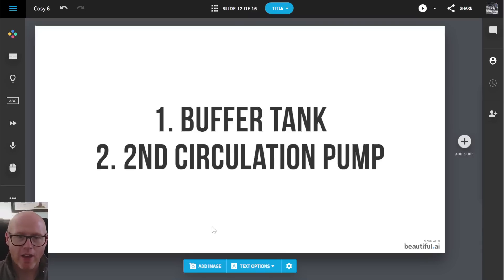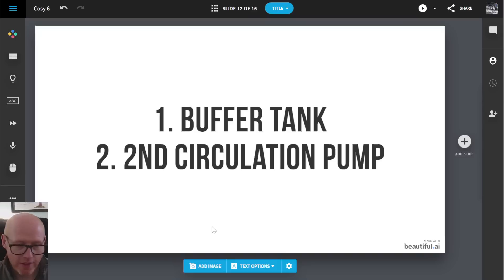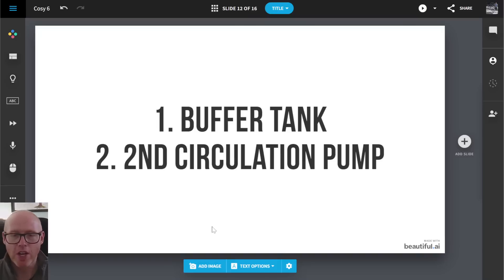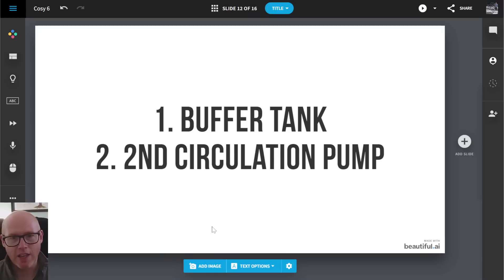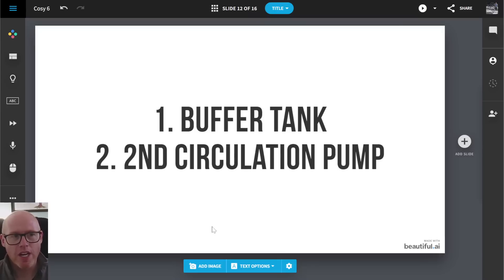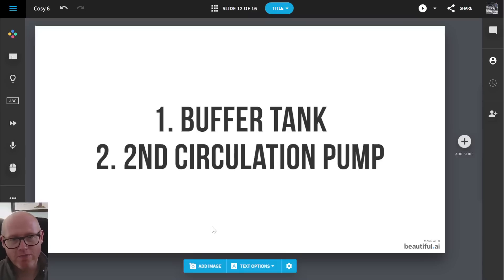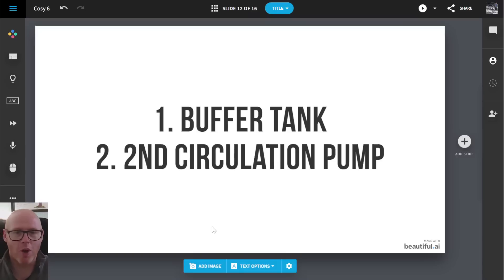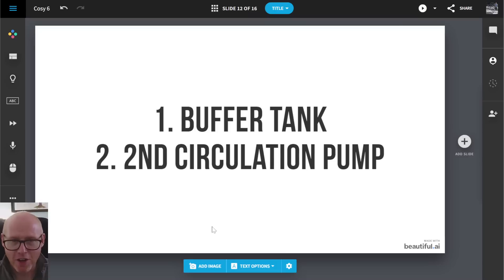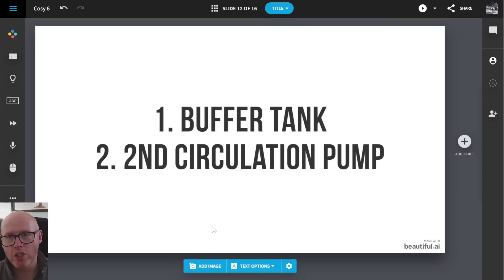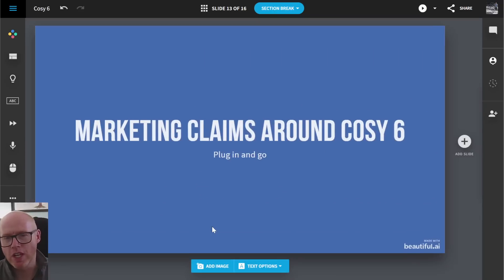So they've added a buffer tank and they've added a second circulation pump. So now they are hydraulically separating the heat pump circuit and then the heating circuit inside the building. I'm not against buffer tanks. So I know there are a lot of anti-buffer tank people there. We've got a buffer tank in our house. It works okay. We're lucky that the flow rates aren't massively different. So we don't have a lot of distortion. But they are kind of idiot proof. You can put them in and the house side will just work out its flow rate and do what it needs to do. And the heat pump can just kind of do what it needs to do and work out its side. I know that's an oversimplification. There's a lot more to it than that. But it's a great way to kind of look to resolve this thing.